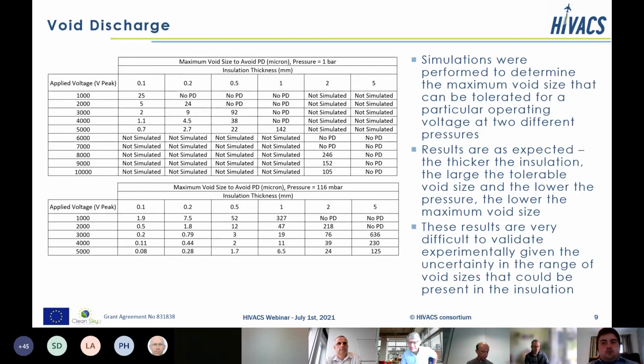So in this table, there are a lot of results here. It shows the maximum void sizes that you can tolerate within the insulation for a particular operating voltage at two pressures. The top table is sea level 1000 millibars, and then the bottom table is 116 millibars again.